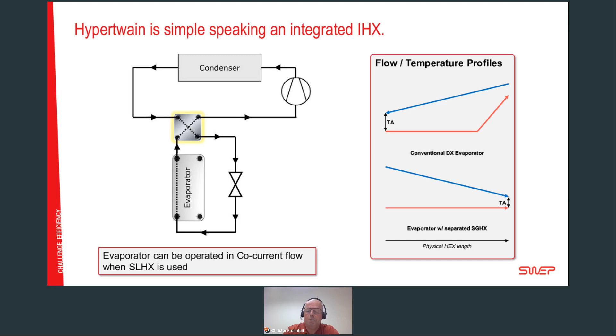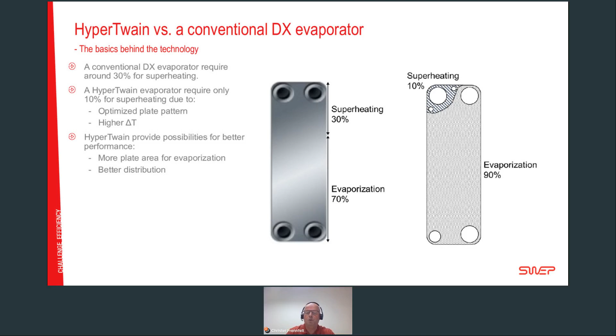And then you get the graph on the right hand below, where you can see that the temperature approach is much closer, and it makes it more efficient. So if you focus on that small heat exchanger in the middle, when I change to the next slide, here is the whole point with the Hypertwain plate, where you have this superheater, liquid cooler, whatever you would like to call it, integrated in the plate, which allows you to add much larger surface for evaporation compared to a conventional one where you have 70% evaporation and 30% of the heat transfer area is superheating. The Hypertwain allows you to have much more evaporation area and a more efficient evaporation temperature. And how does this work in the system?